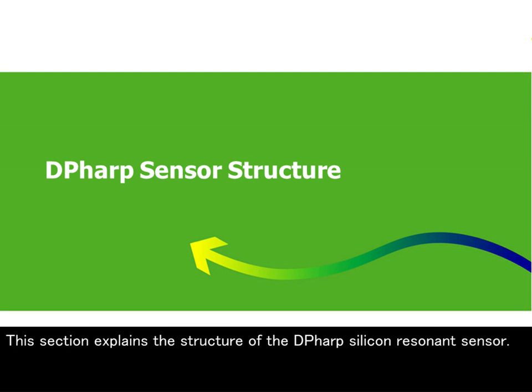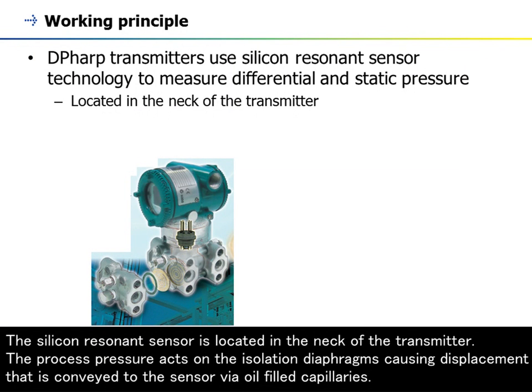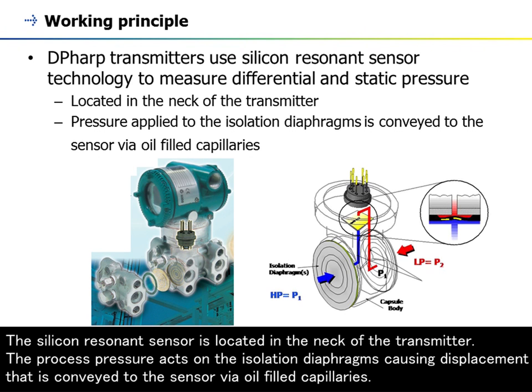This section explains the structure of the DPharp silicon resonant sensor. This silicon resonant sensor is located in the neck of the transmitter. The process pressure acts on the isolation diaphragms causing displacement that is conveyed to the sensor via oil-filled capillaries.